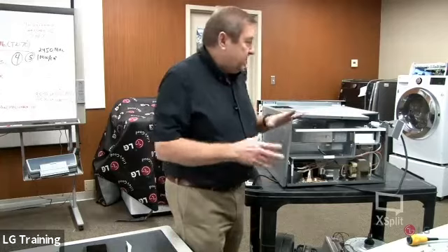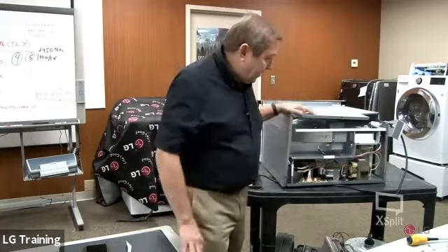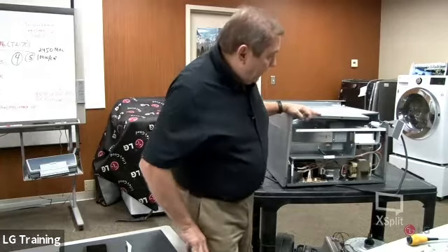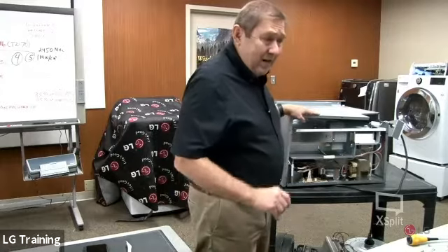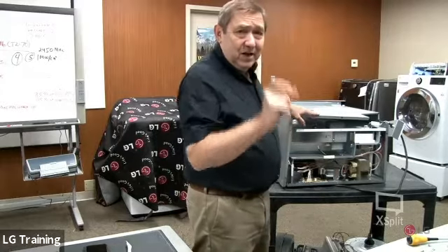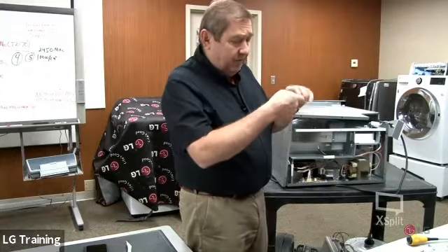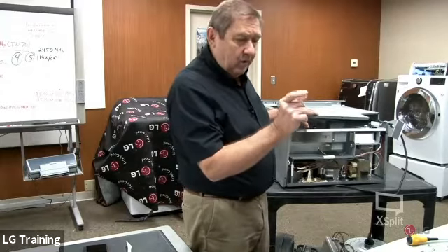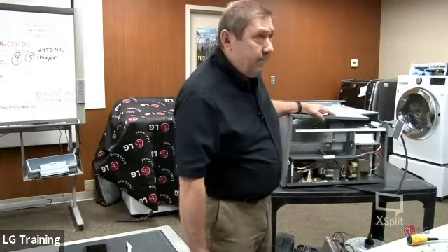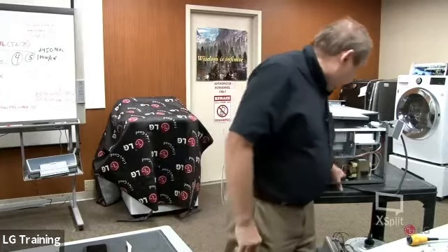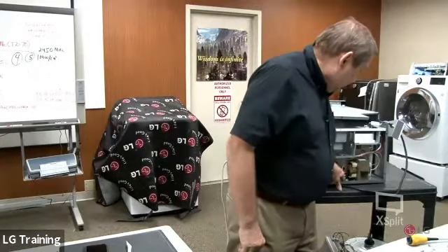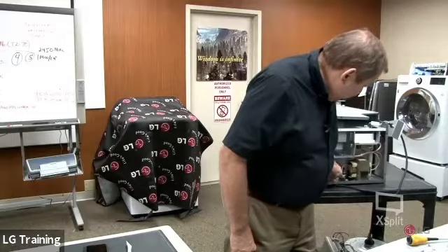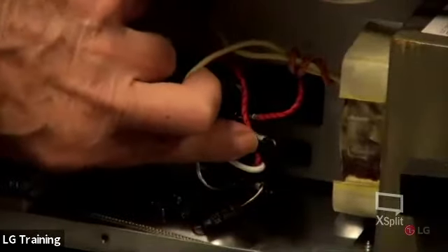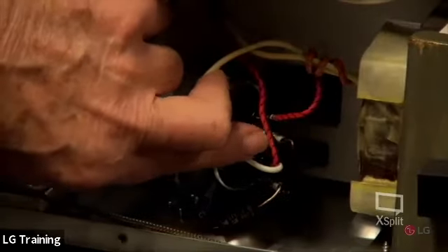I've had technicians call me and say I replaced everything and it's still not heating. They replaced everything on the high voltage side, but what they didn't do is check to see if that fuse was open. It's got a fuse holder, just opening it up - it's a weird looking fuse. The diode is right here, so there's the two - this is your main diode, and there's the secondary one. This goes from one terminal to the opposite terminal.